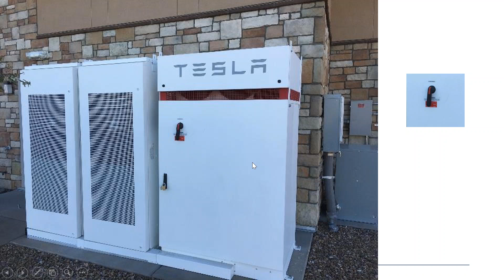If you happen to be using an energy storage system for a 1 or 2 family dwelling, then that disconnecting means or its remote control shall be located at a readily accessible location on the outside of the building. The best bet is probably near the building service, because that's where other disconnects belong. Again, the disconnect can also be integral with the energy storage system. In this case, this unit has a disconnect built into it.